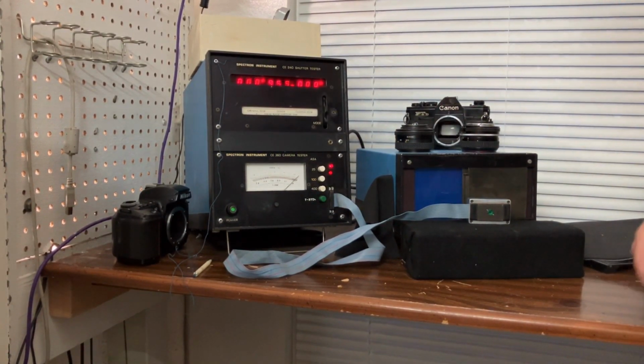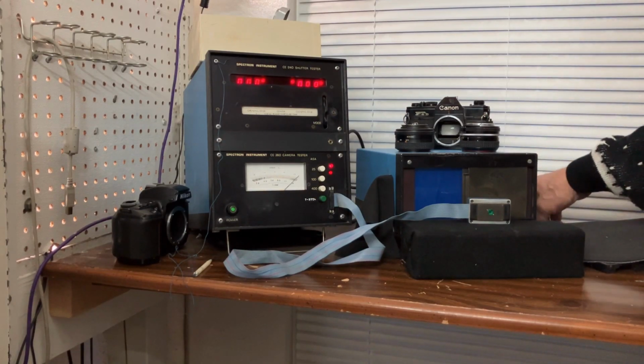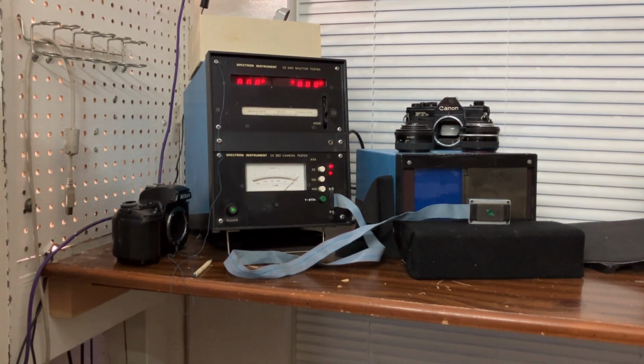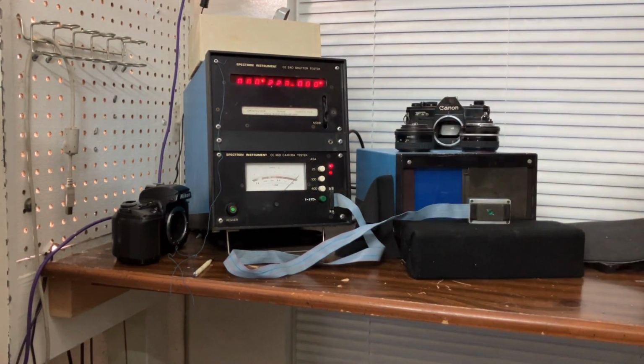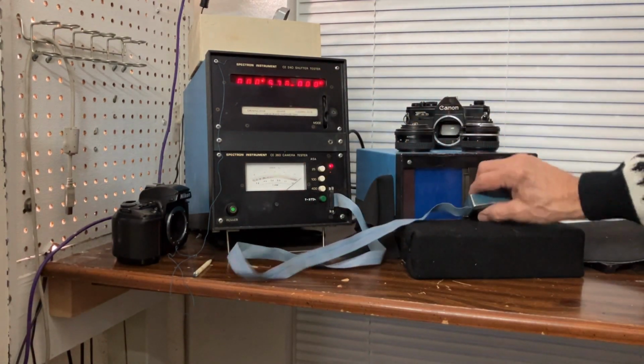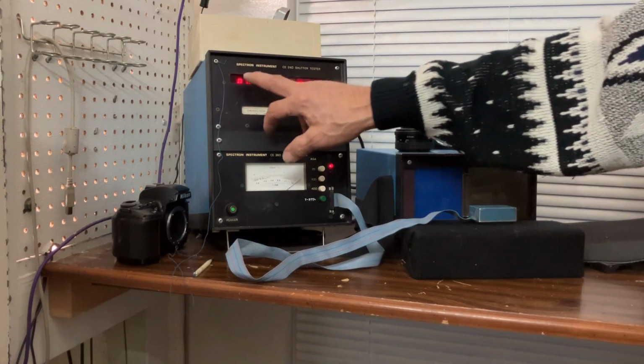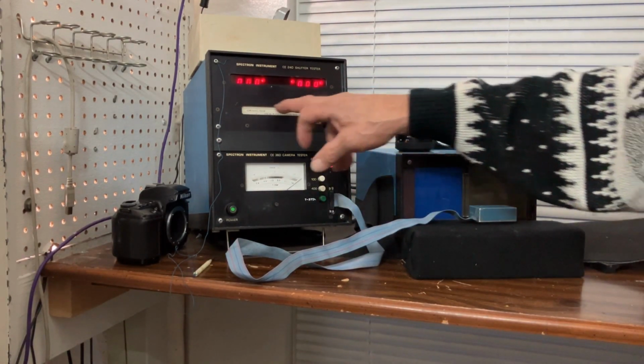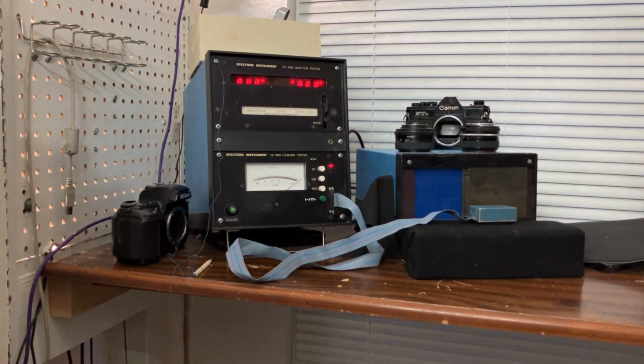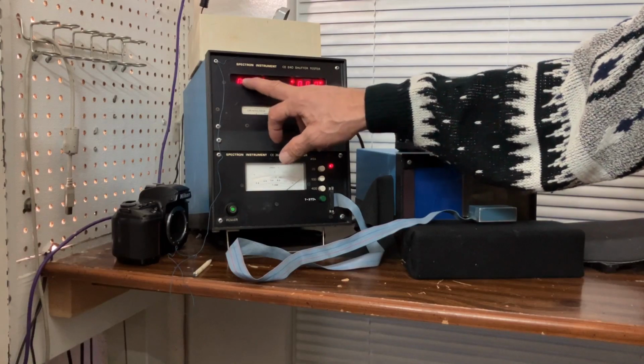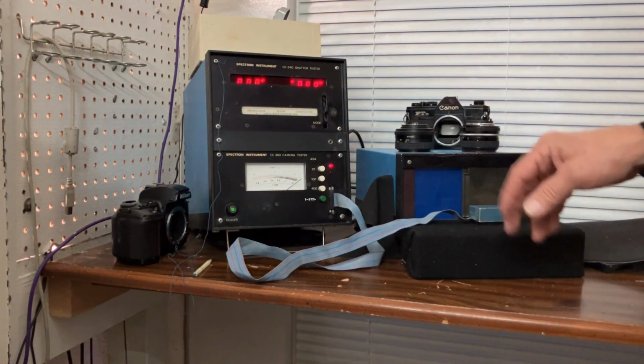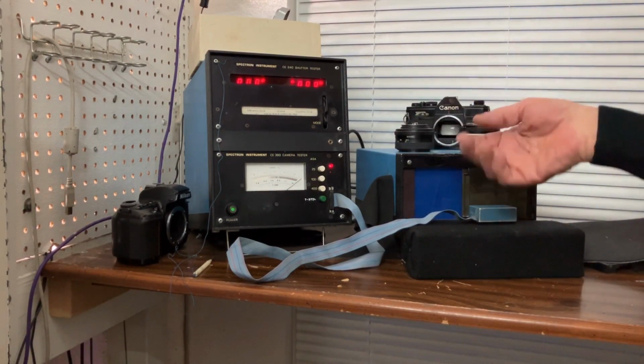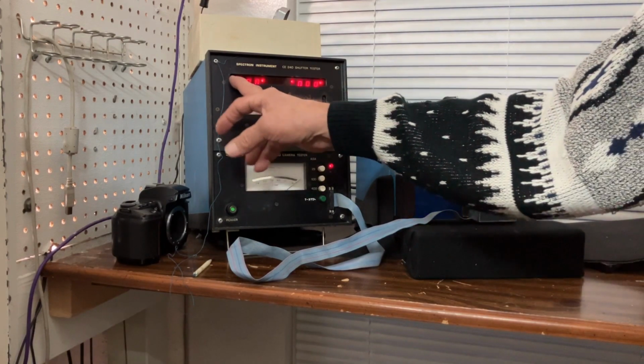Okay, so come back over here. I'll point out some of the features of the tester. I'm going to grab a pair of tweezers. I like pointing at something with a pair of tweezers more than anything else, just because I use them all the time. Anyway, up here is the shutter speed. It's just clocking now because nothing's seeing the sensor, but it reads milliseconds. Right now the tester is dialed up where you're seeing 1.00. So if you were reading a second, it would be 1 second, 0.00 milliseconds. If we're testing a shutter at a thousandth of a second, we're not interested at all in the decimal point being here. We're interested in the decimal point being there.